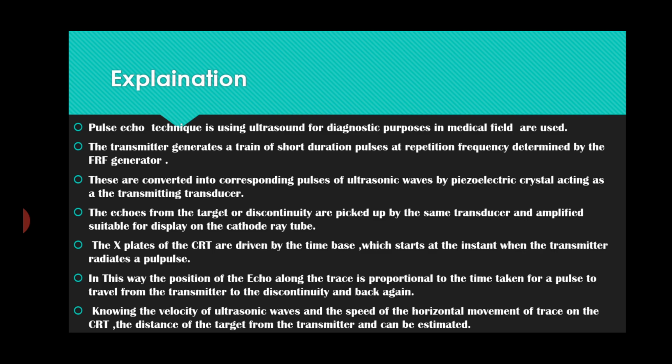These are converted into corresponding pulses of ultrasonic waves by a piezoelectric crystal acting as the transmitting transducer. The echoes from the target or discontinuity are picked up by the same transducer and amplified suitably for display on the cathode ray tube. The X plates of the CRT are driven by the time base, which starts at the instant when the transmitter radiates a pulse.